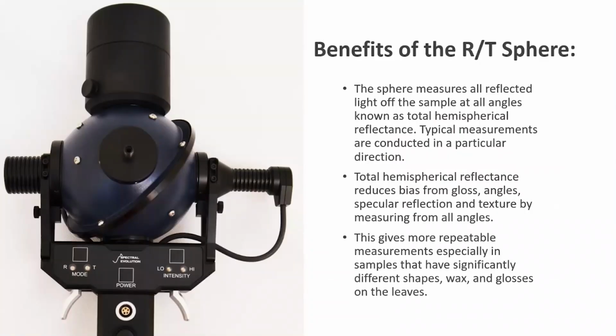And then we also have an RT sphere. The sphere measures all reflected light off of a sample at all angles. This is known as total hemispherical reflectance. So this would be best used for any samples that have gloss or very angular features. If you have a very dried out leaf or something similar, this will measure the light in all directions bounced off of the sample. So it'll give you a leaf reflectance measurement that can be better trusted, or if it's waxy and you get more specular reflectance, this would be the best way to measure something that's very specular.